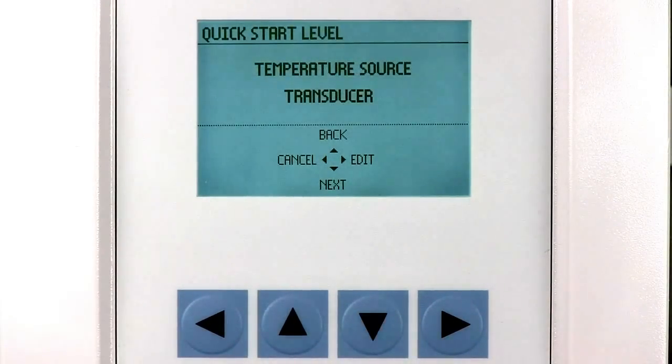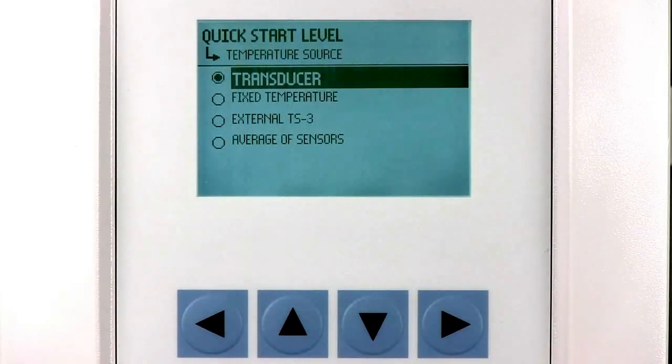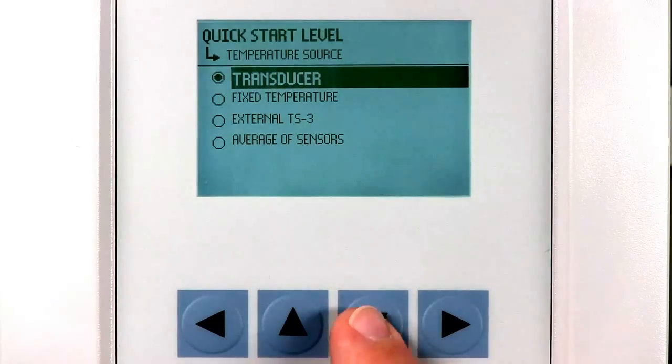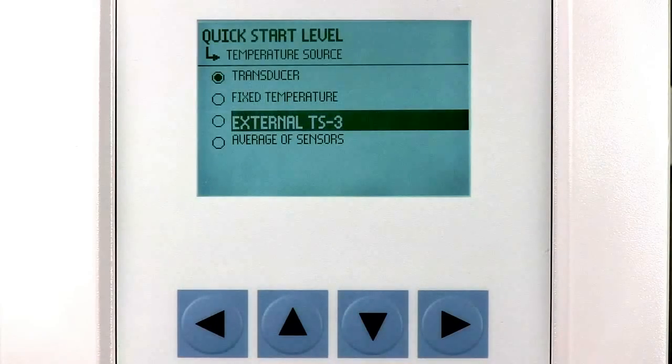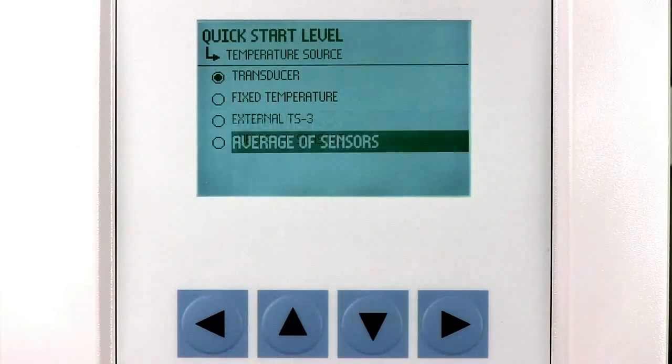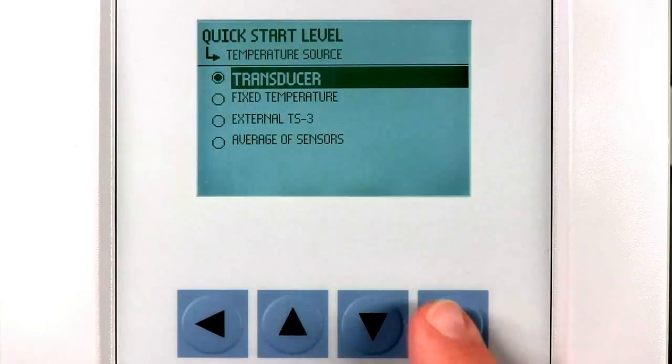The LUT400 uses a temperature sensor to automatically adjust for speed of sound changes within the measuring atmosphere. We can use the sensor built into the Echomax transducer or an external TS3 temperature sensor. Another option is the average of both transducer temperature sensor and the TS3. We will use the transducer selection for our application.